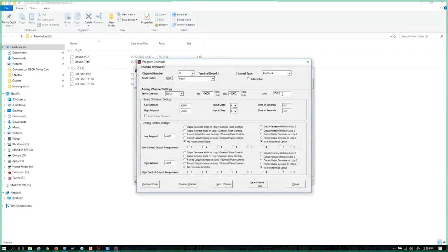And now it does say PSIG. I don't remember changing it. Maybe it changed it automatically. Oh, no, take that back. When you select other, it generally takes the last default that you were dealing with in the program for any program file when you're setting up a new channel, and selects that unit of measurement here for you automatically. That's what happened here. It's no longer selected from a drop-down, so you can scale this to anything you want when it's scaled as other.